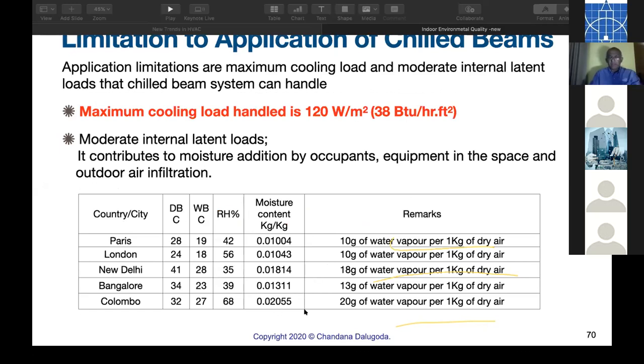See, I have given some examples. In Paris, summer, 28, 19, 42 RH, this is the moisture content, 0.01. London, 0.01. New Delhi, 0.018. Bangalore, 0.013. But Sri Lanka, 0.02. So it's double. That means 10 grams of water vapor in 1 kilogram of dry air. In Sri Lanka, it is 20 grams of water vapor per 1 kilogram of dry air. So that is a problem.